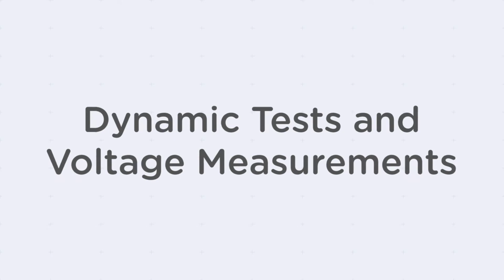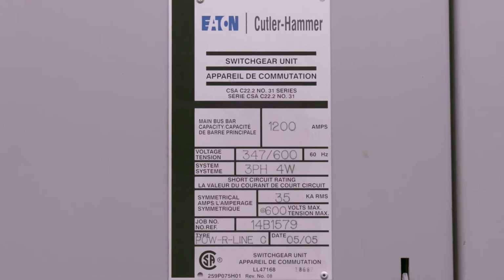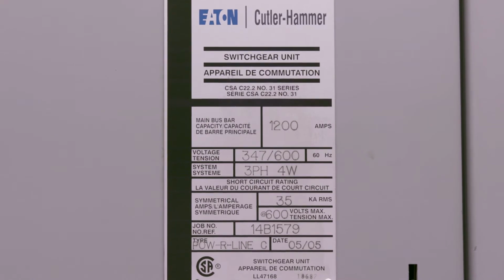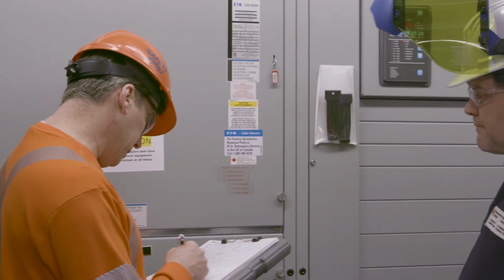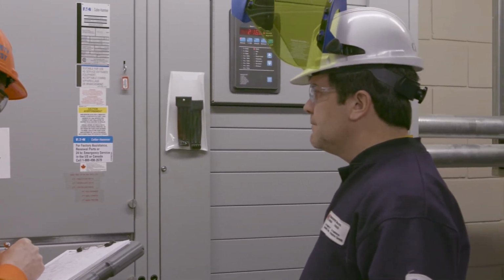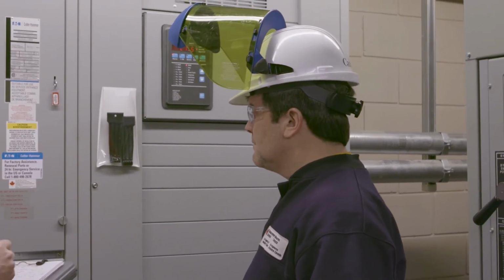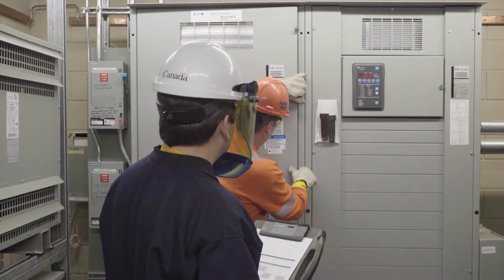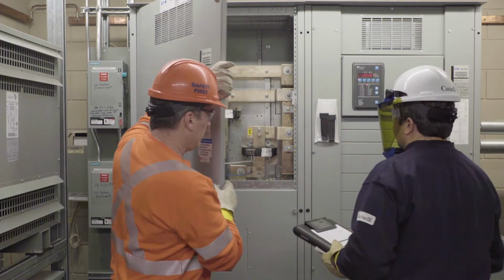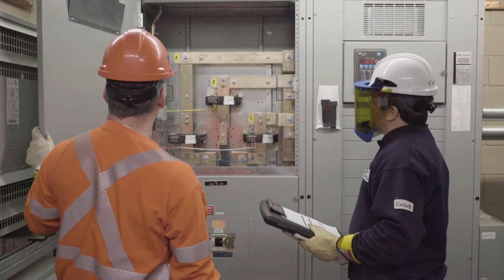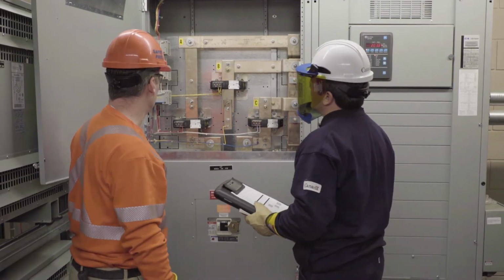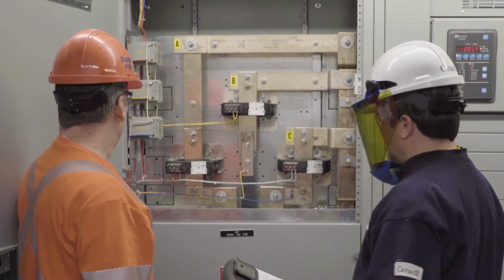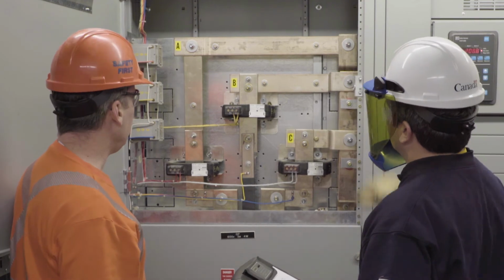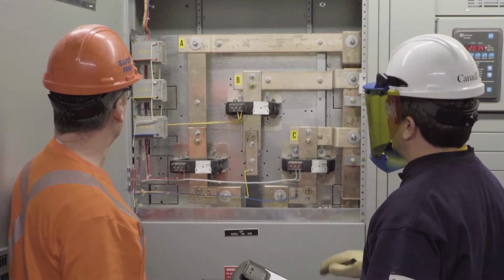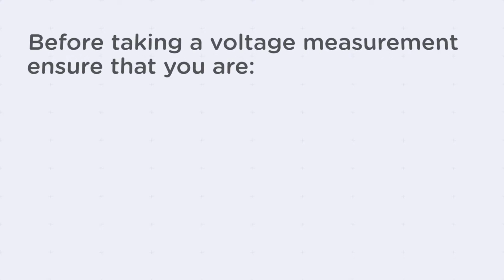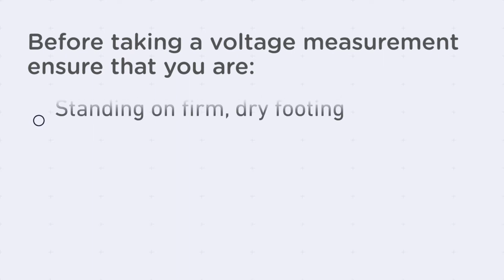Before taking any voltage measurements, visually re-verify the voltage rating of the service to be measured. Also, re-establish or confirm the line and load sides of switches from which measurements will be taken. You should always take voltage measurements on the load side of the main switch.